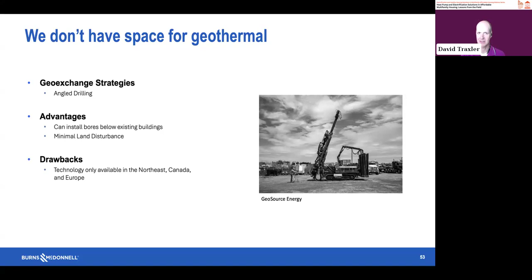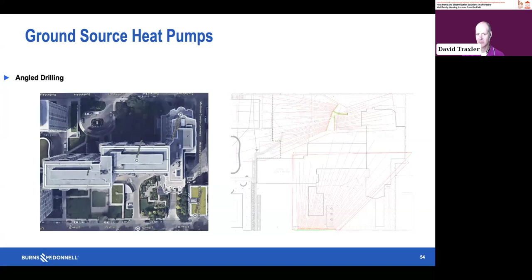This is an actual example: a 25-story multifamily building in an urban setting. You can see there isn't a lot of green space around this building. But what they did was cut out a small patch on the lower side of the lot, and on the upper side, where there's some trees and a courtyard, they cut another patch. From there, they spread the bores out underneath the buildings. So even though this building was constrained by a lot that didn't have much space for a traditional ground source system, it was able to provide a significant amount of energy and put a ground source heat pump system in this location.